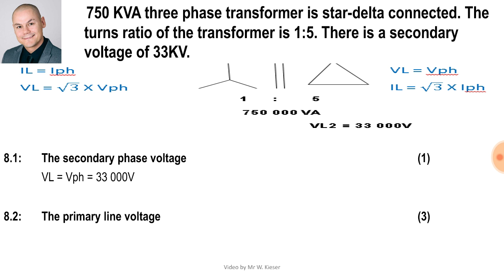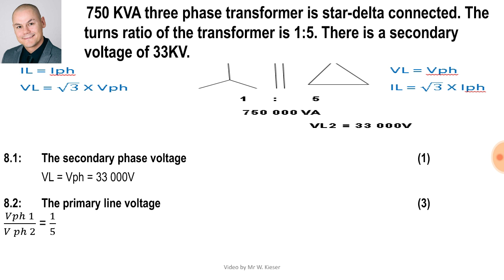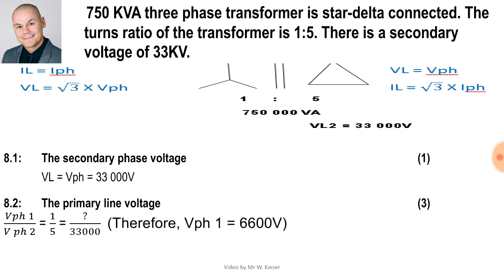To calculate the primary line voltage, we use the equation V phase one over V phase two. The ratio is 1 to 5 and the secondary phase voltage is 33,000 volts. The factor that goes into 33,000 five times is 33,000 divided by 5, which gives us 6,600 volts for V phase one. We can double check: 6,600 goes into itself once and into 33,000 five times. Now to calculate the primary line voltage: it's square root three times the phase voltage of 6,600, giving us 11,431 volts.